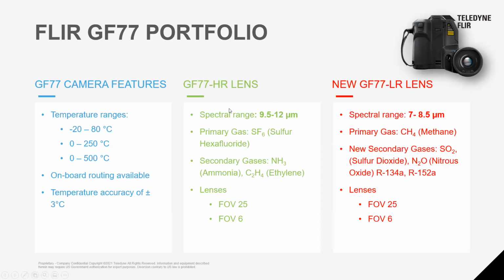Then our HR lens, our high range lens, has a spectral range of 9.5 to 12. The primary gas here is going to be SF6, and it can also pick up secondary gases: ammonia and ethylene. You can get these lenses in a 25 degree or a 6 degree. Similarly on the low range side, the spectral range is 7 to 8.5 microns. That's what it's tuned to. At these wavelengths, the primary gas we're able to pick up is methane, with secondary gases of sulfur dioxide, nitrous oxide, and a couple of refrigerants, 134A and 152A. Again, available in 25 or 6 degree lenses. With the 6 degree lens, if you're shooting objects at a greater distance, you're going to want that narrow focus lens.